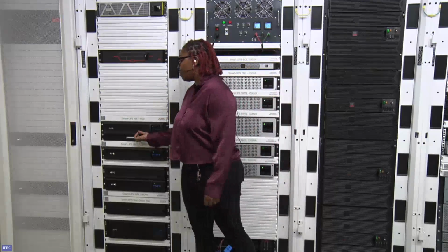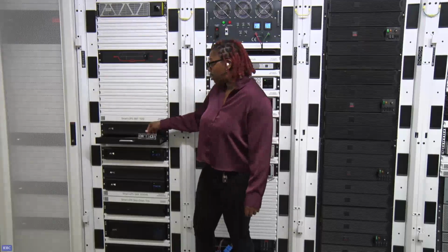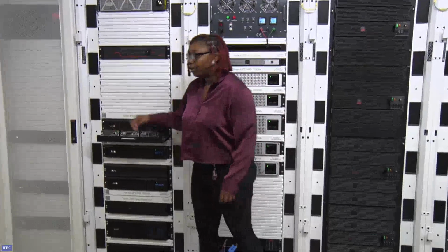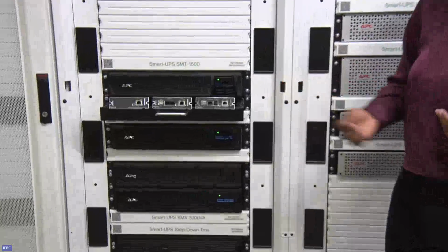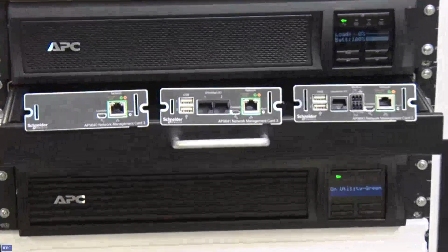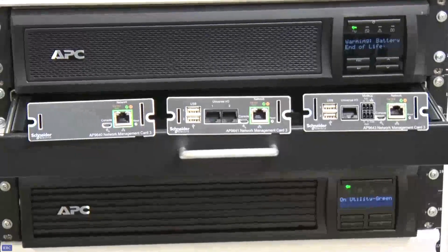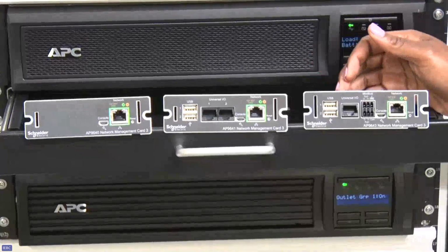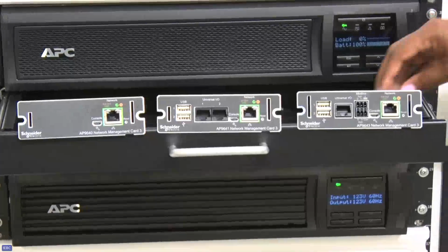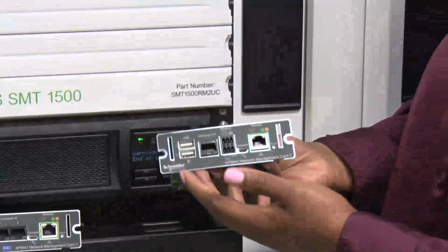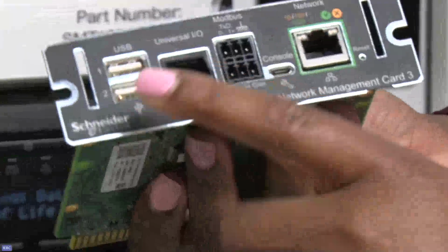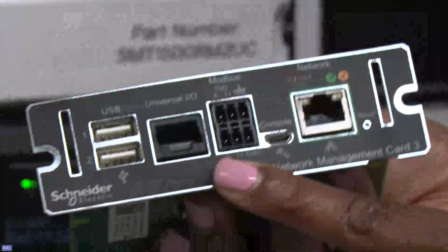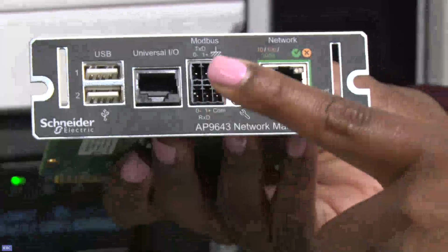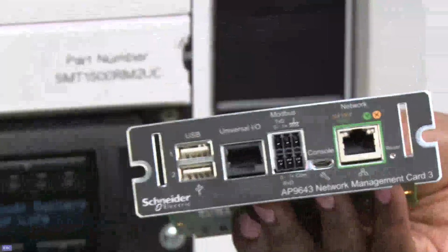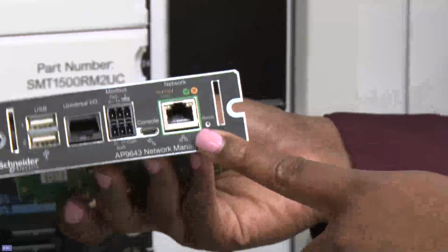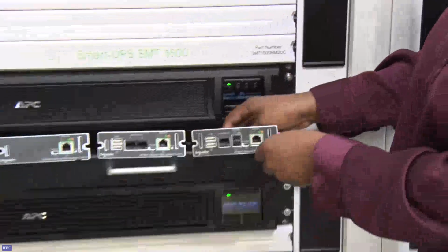With these particular UPS systems, we have network management cards. Some UPS systems only let you monitor them, meaning you can see what's going on inside and read what's coming out. But with these network management cards, you get manageability, letting you send directives to the UPS system. This one has USB ports, universal IOs for things like temperature sensors, Modbus connections for serial communications, and a standard network port for monitoring.